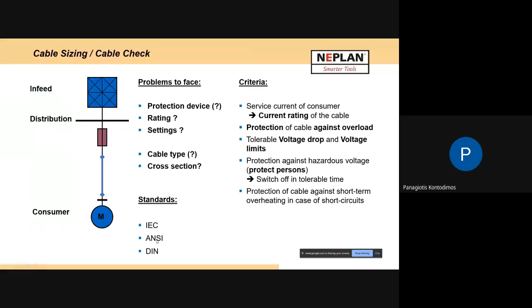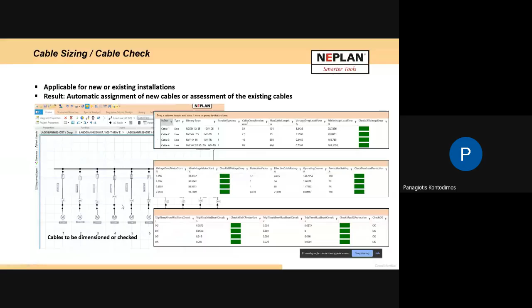Or in an existing installation, we can check if the cables we have pass all the criteria. So we can say, according to the cable check, the cables that we have are sufficient for these motoric loads.